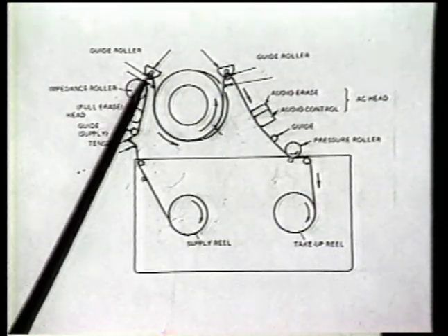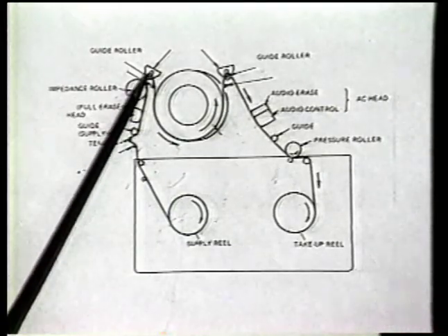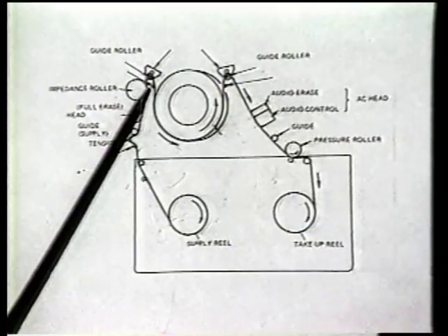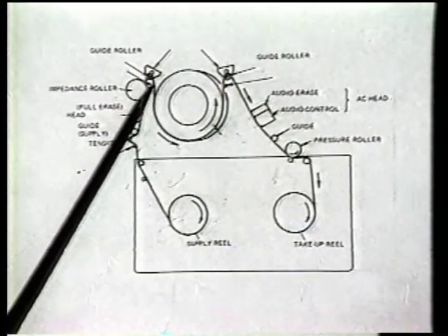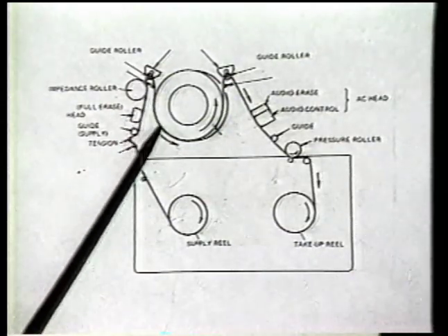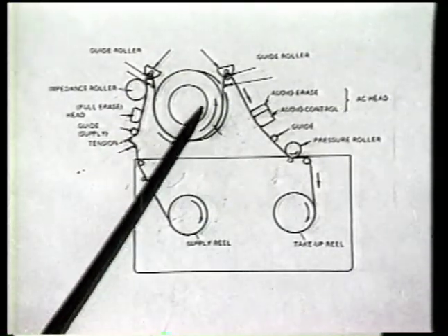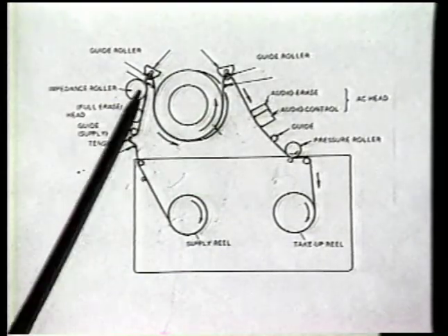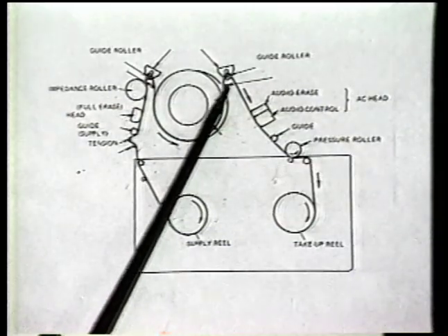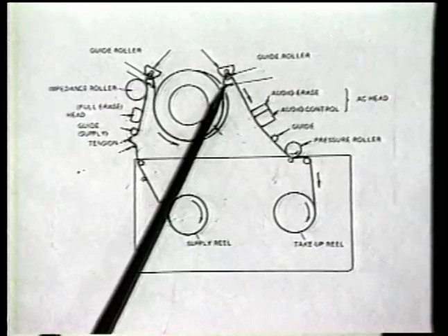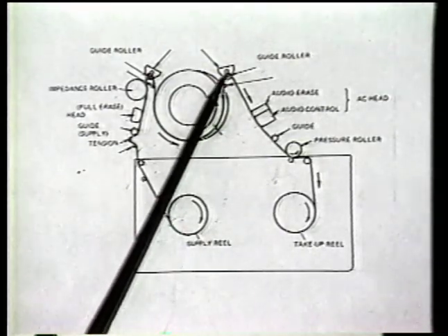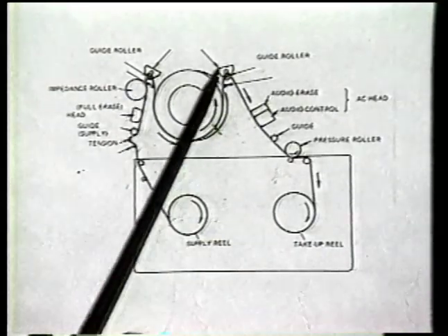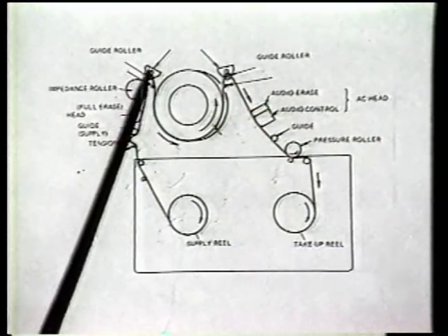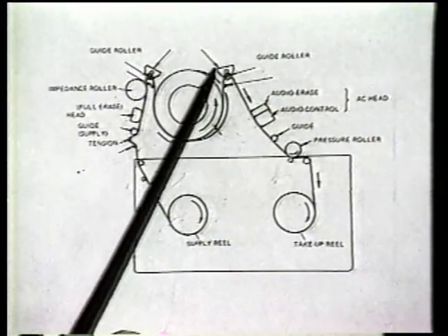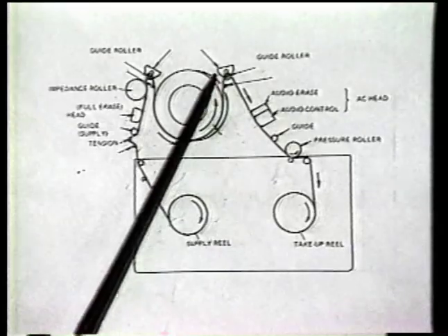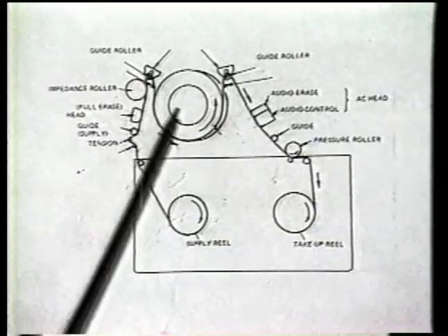Coming into, again, the P2 guide, which we referenced earlier that started here, pulled the tape around the video drum, into the entrance slant guide. This is the final guide before the tape actually goes into the video head. The slant guide sets the geometry of the tape up so that the tape hits this drum so that it's flat across the face of the drum. The drum rotates at the same direction that the tape is coming from. So as we come out of the video drum, we have another slant guide, again, to maintain the geometry of the tape going through the heads. We come into what's called P3, typically the P3 guide. By the way, both P2 and P3 have nested themselves into the V stoppers. There's an entrance V stopper and exit V stopper. We'll show you some of those again in a few minutes, but don't move those V stoppers in general. Those are very critical that they set up the proper geometry for the rest of the machine.